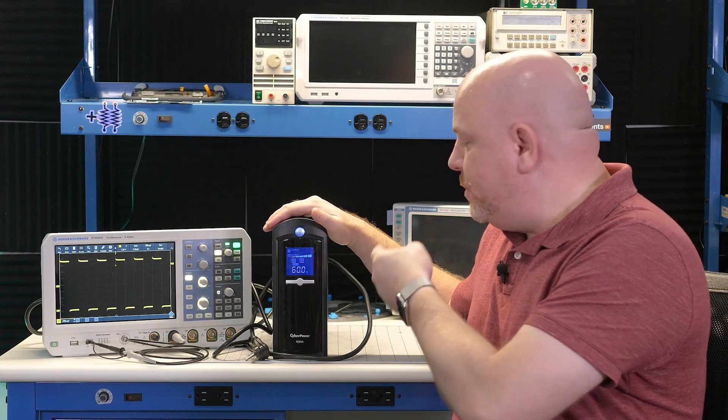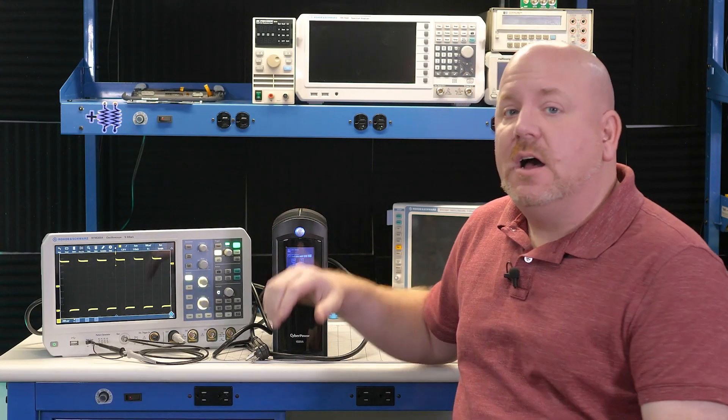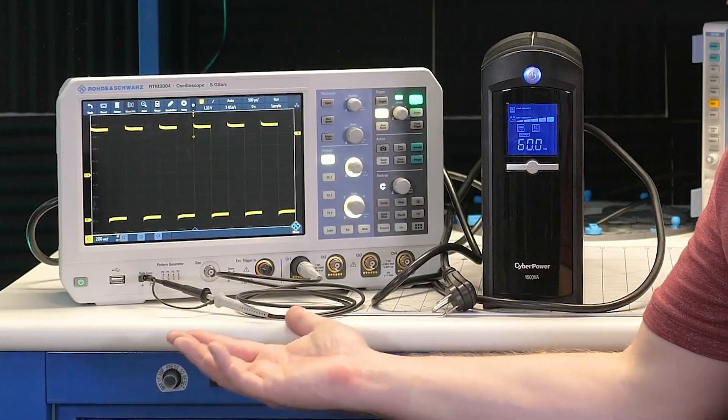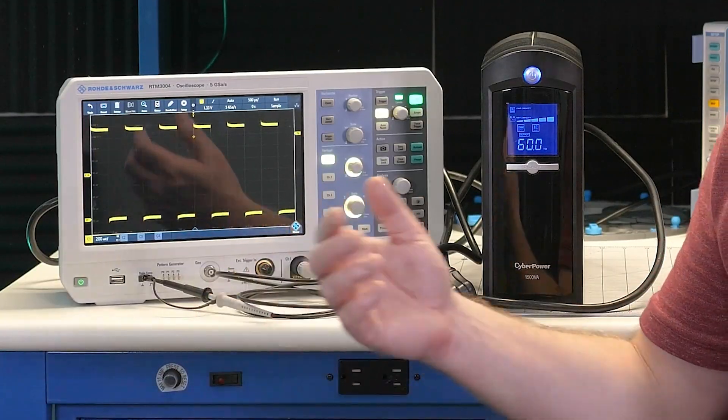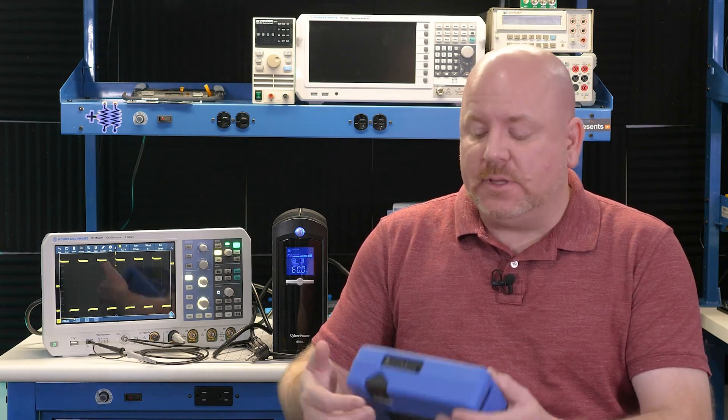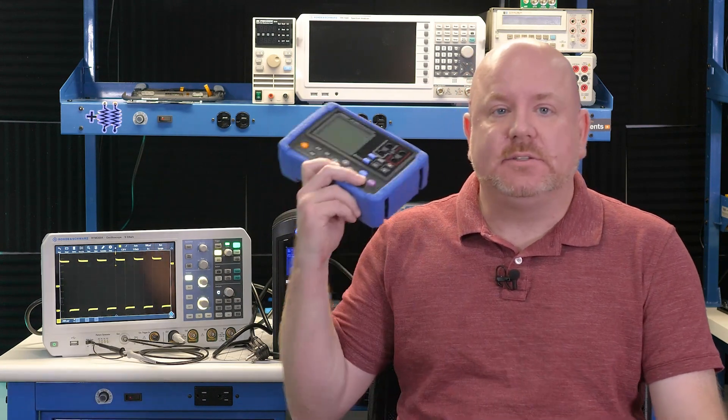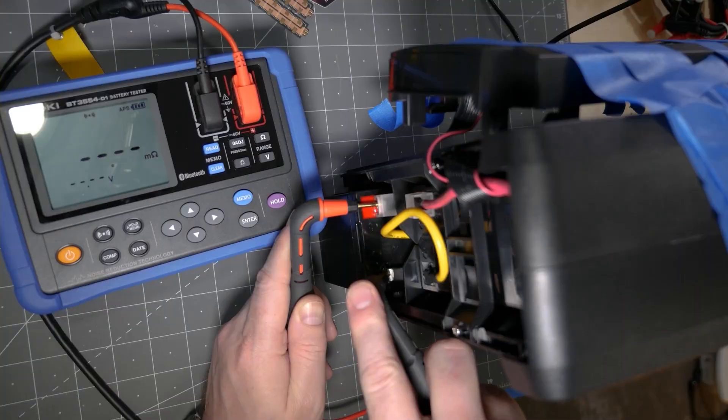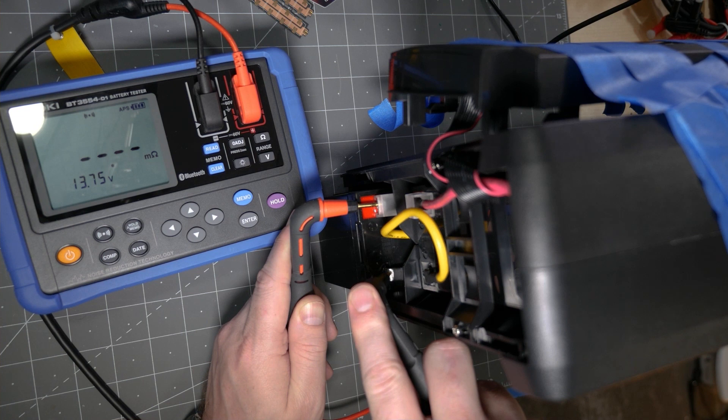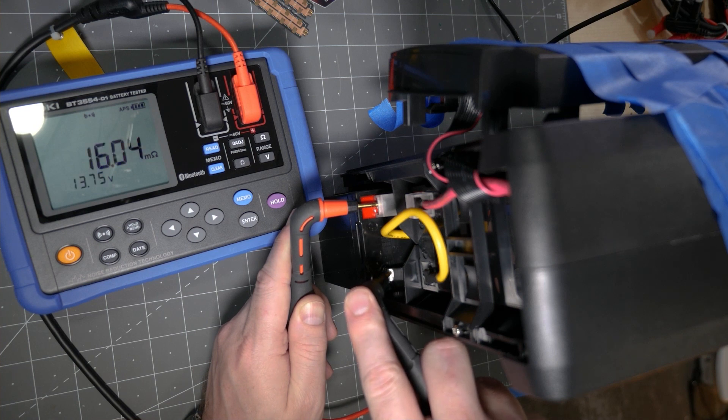This box is an uninterruptible power supply or UPS. Using a lead-acid battery, it provides power to devices like my scope when AC mains goes away. Over time those batteries wear out and need to be replaced. That is where this Hioki battery tester comes into play. Not only can it tell us the ESR of a sealed lead-acid battery, but it can also measure while the battery and UPS are in operation.